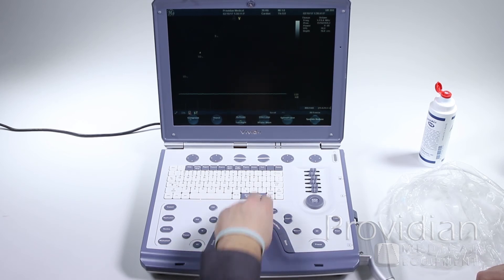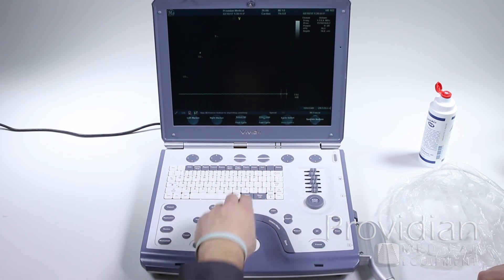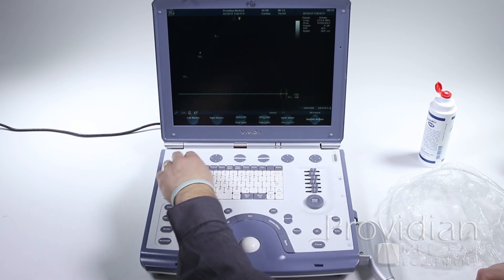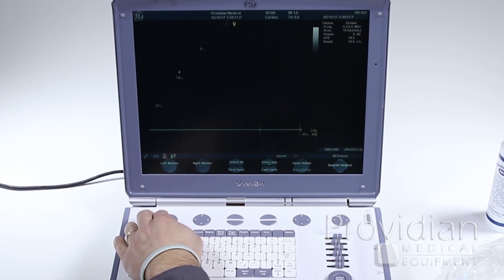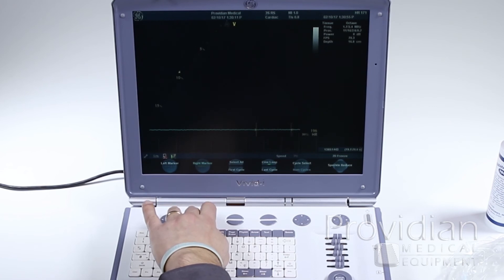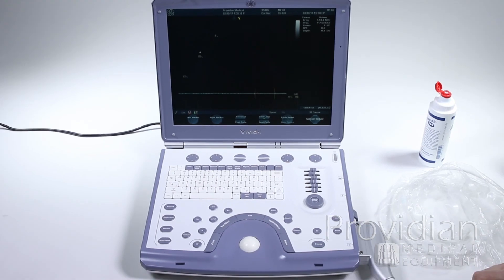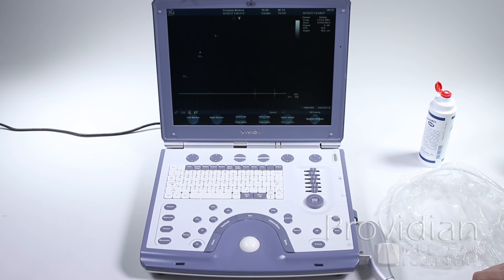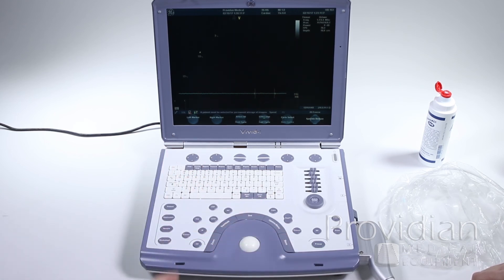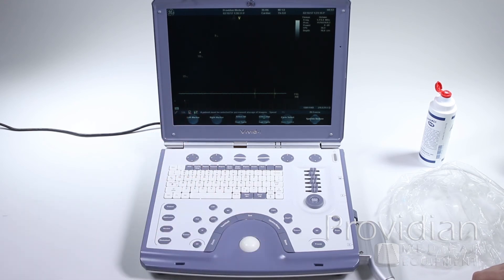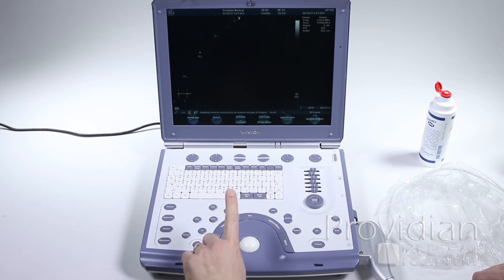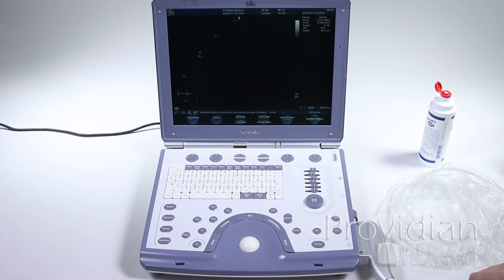So now I can also save that loop. I want to go to the cine loop menu. If I only want to save a certain portion, I can change this left marker, move it to the left or to the right, and the right marker. I can save just a portion of this cine loop instead of the entire thing, so that way it won't fill up my hard drive. If I just want to select this part and I want to save that cine loop, I'm going to hit the store key. That's going to actually save a loop. You can see it kind of looks like a film strip down there. If I freeze again and just do a single image and hit store, it's only going to store a single image.